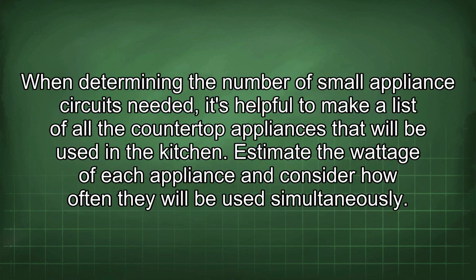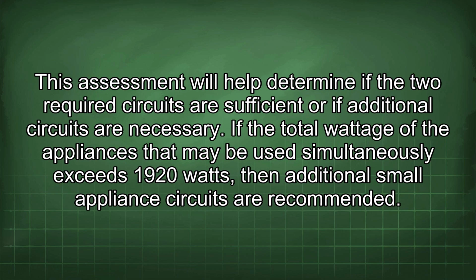When determining the number of small appliance circuits needed, it's helpful to make a list of all the countertop appliances that will be used in the kitchen. Estimate the wattage of each appliance and consider how often they will be used simultaneously. This assessment will help determine if the 2 required circuits are sufficient or if additional circuits are necessary. If the total wattage of the appliances that may be used simultaneously exceeds 1920 watts, then additional small appliance circuits are recommended.